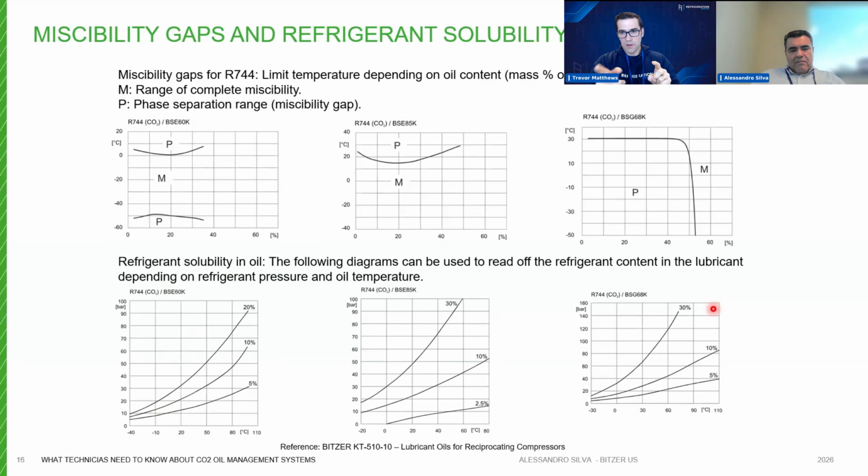Okay, I love that. So we got a question in there, and I hear this a lot. Why do compressors, and it doesn't matter if it's Bitzer or not, why does the Bitzer CO2 compressor pump out a lot of oil? One thing could be due to heat. If you're running really hot, 310 degrees Fahrenheit or 150 degrees Celsius, you thin that oil, so you're just going to pump more oil. Is that correct if I say that?